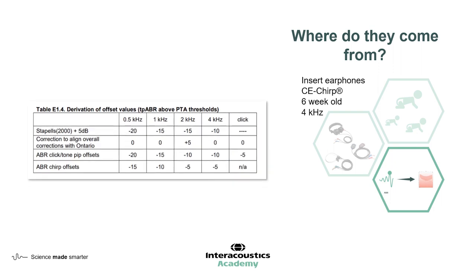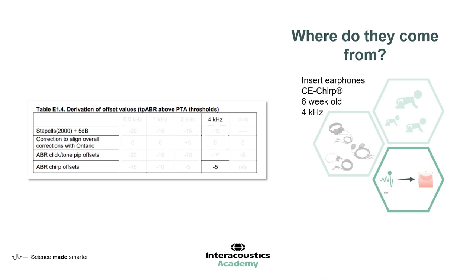So we have our ABR offset, our transducer corrections, divided up into different age groups. The authors of the BSA correction factors paper brought these together — let's look at how this works. Let's take just one example: insert earphones, CE chirp stimulus, testing a six-week-old at four kilohertz. First, we need our ABR offset — from the Stapels meta-analysis plus the 5 dB. For four kilohertz, this gives us an ABR offset of minus 10. There was no correction to align with Ontario, and as we are looking at a chirp, we end up with an ABR offset of minus five.